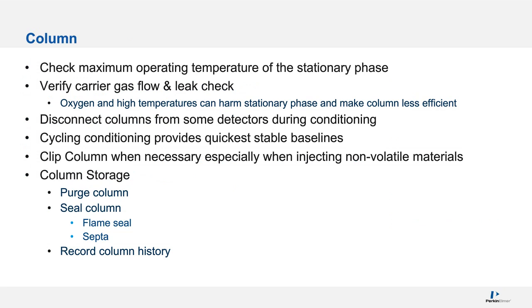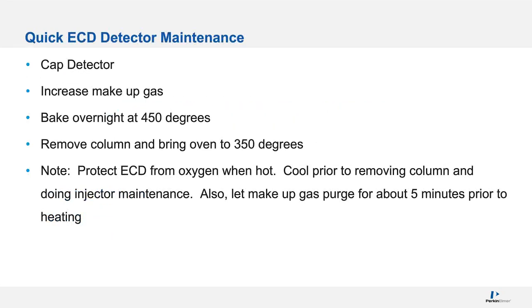With the column, just make sure you don't exceed the temperature that the vendor suggests. And it's recommended to not condition a column in the detector. I know sometimes there's not a choice. And clip the column if you see any non-volatile materials in it, especially if you're doing dirty matrices. I know you guys probably do that more frequently.